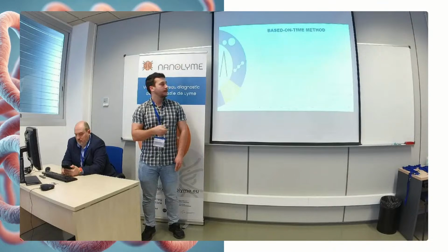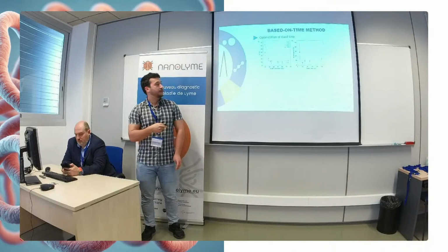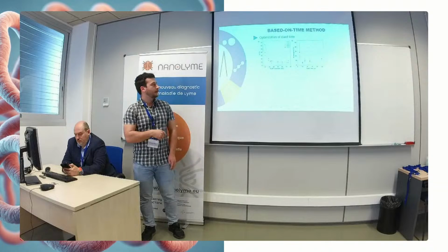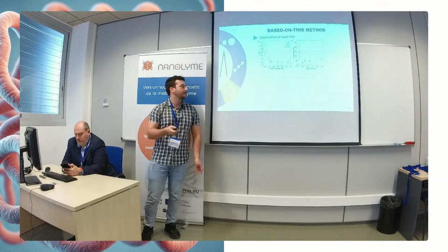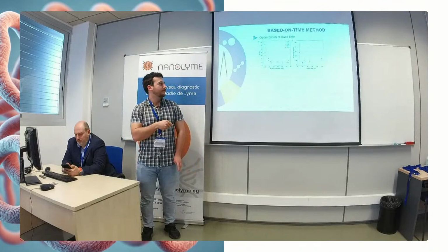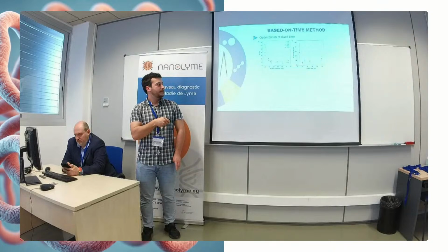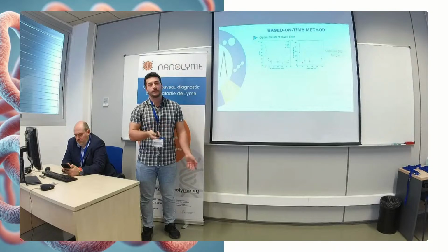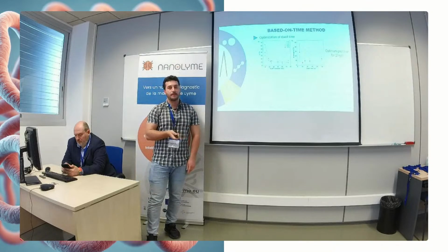So with this idea, we optimized the dwell time, because our instrument, the NexION 5000, allows us to use low dwell times. And we observed that the best results were obtained for a dwell time of 20 microseconds, which was used for the rest of the methodology.